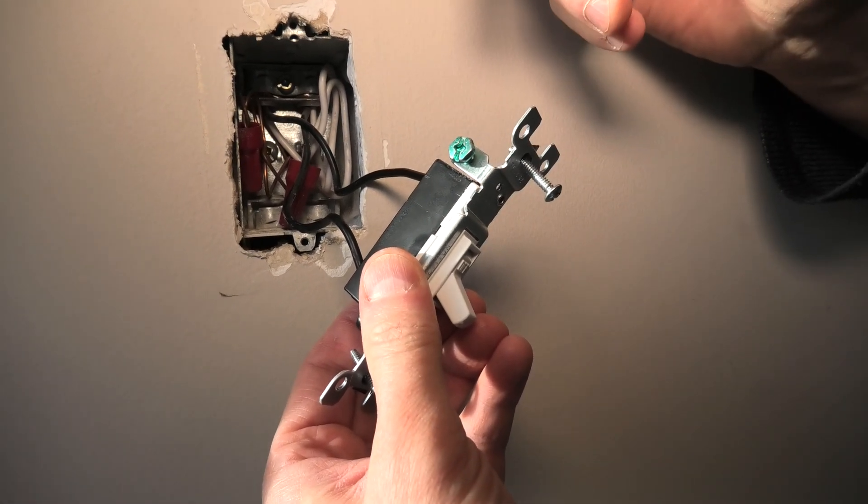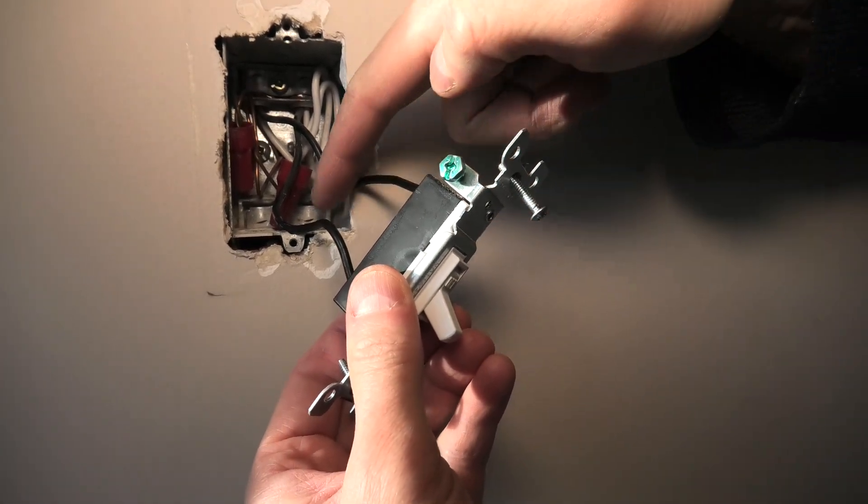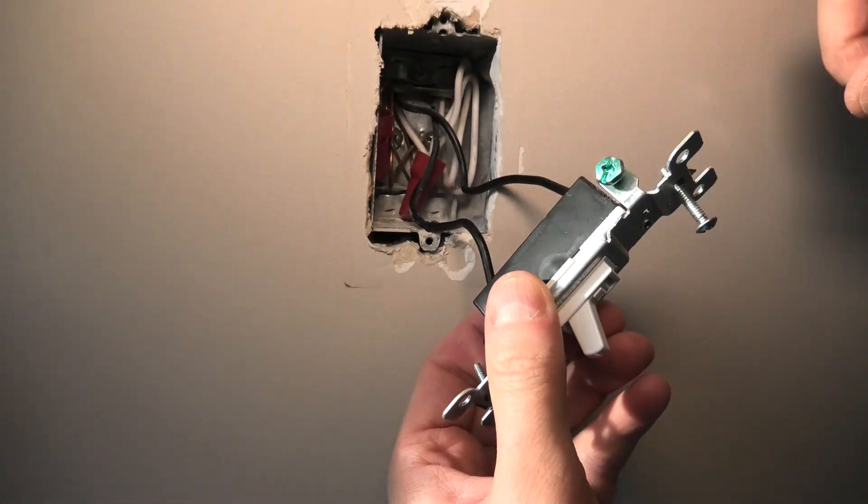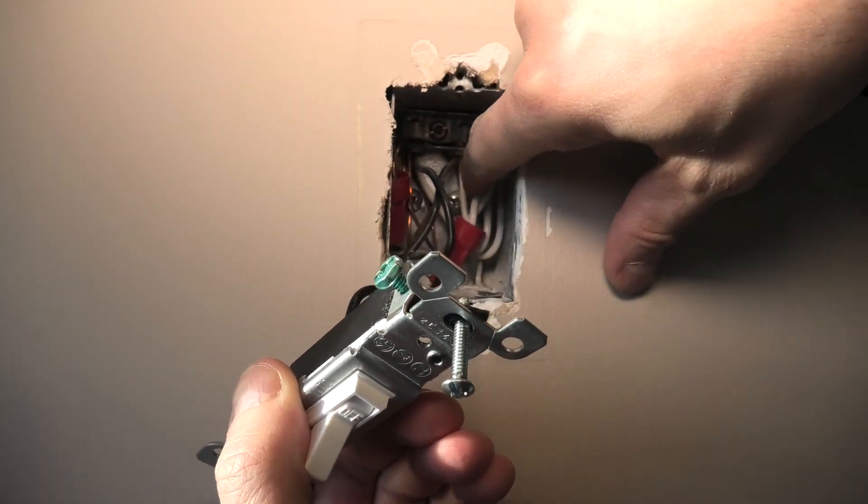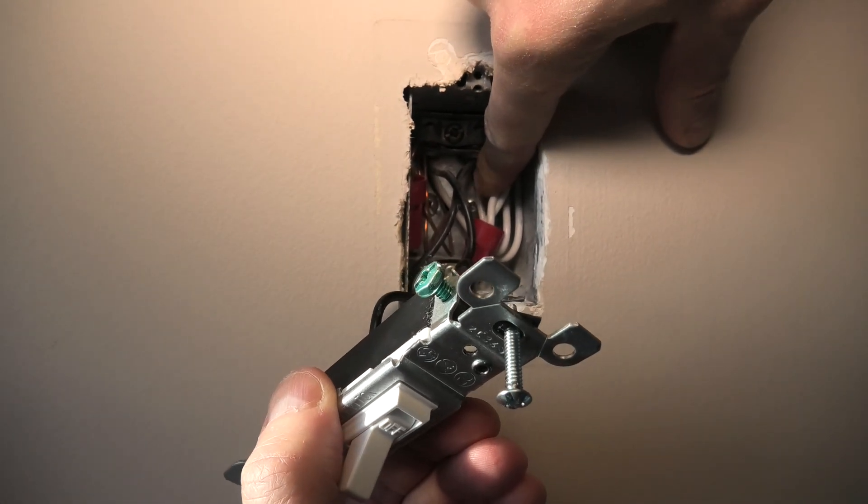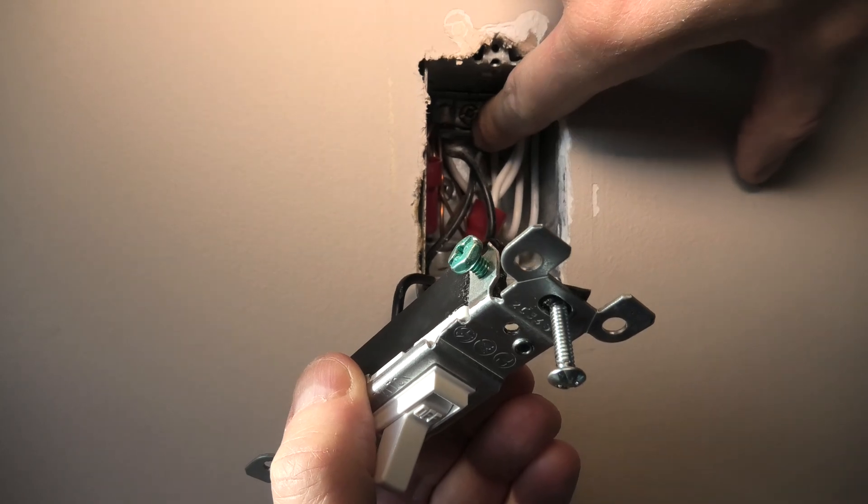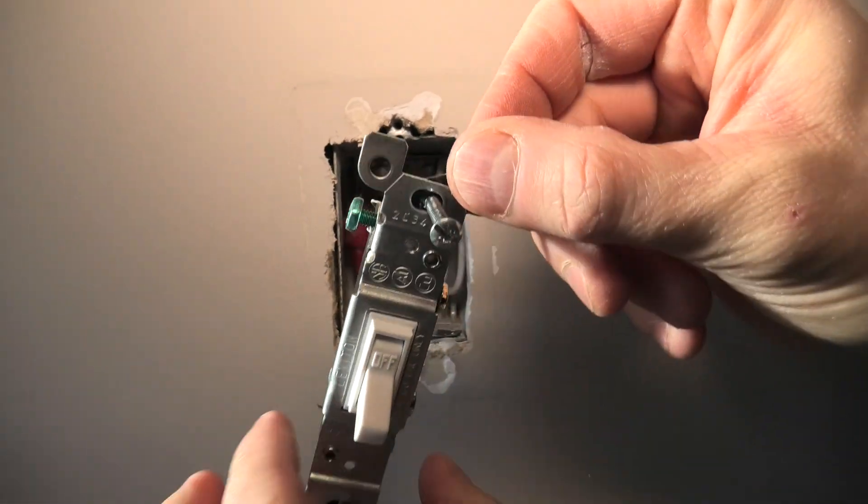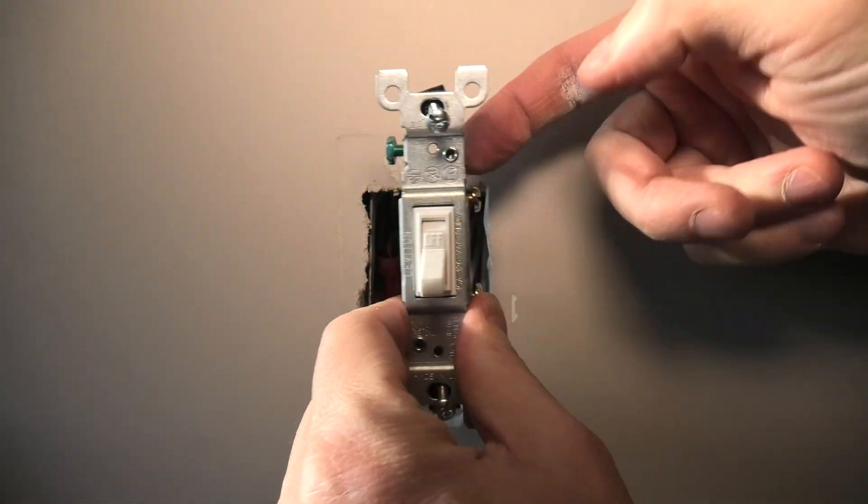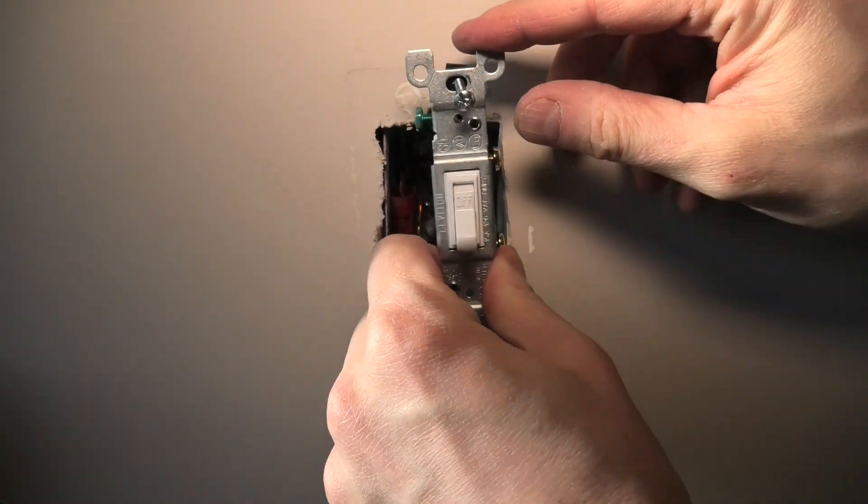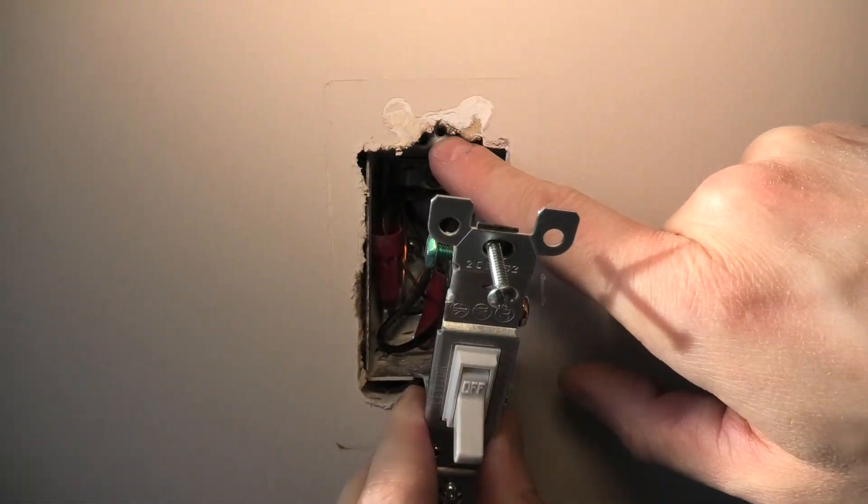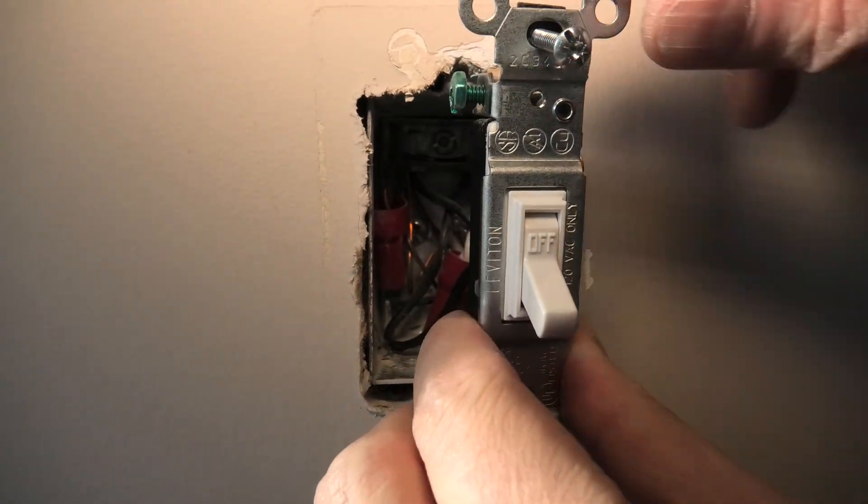In this case, the reason for that is we have a metallic box which is already grounded to that screw over there. You can see the bare wire connected to the screw. This means that the box is grounded, and once we install the switch it will actually touch the box and will be grounded this way.